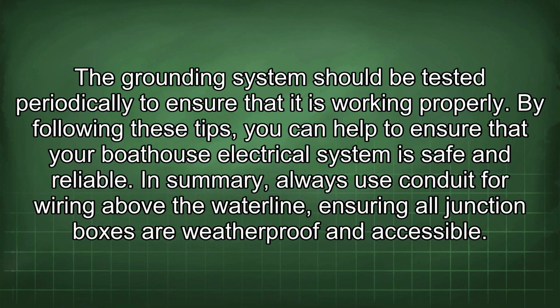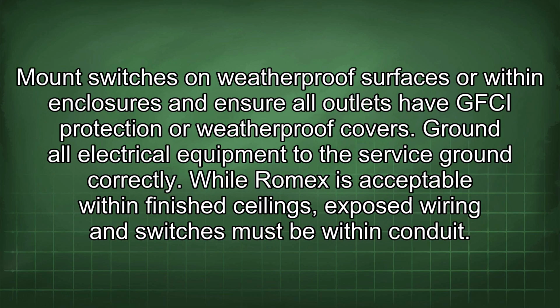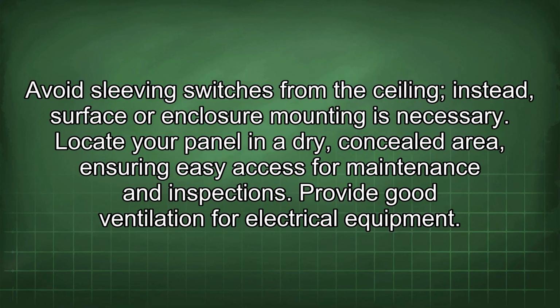In summary, always use conduit for wiring above the waterline, ensuring all junction boxes are weatherproof and accessible. Mount switches on weatherproof surfaces or within enclosures and ensure all outlets have GFCI protection or weatherproof covers. Ground all electrical equipment to the service ground correctly. While Romex is acceptable within finished ceilings, exposed wiring and switches must be within conduit. Avoid sleeving switches from the ceiling. Instead, surface or enclosure mounting is necessary.